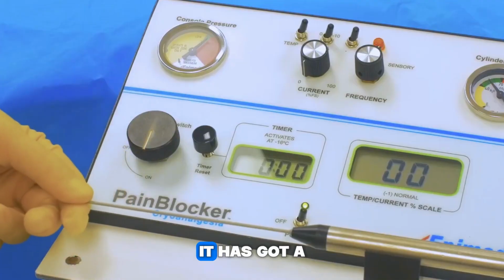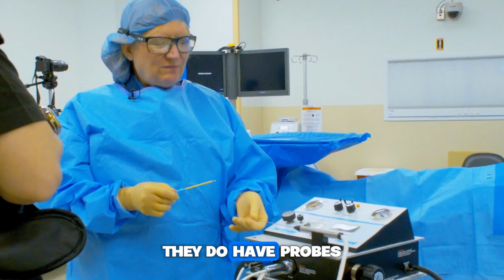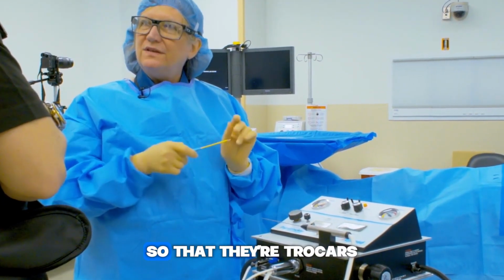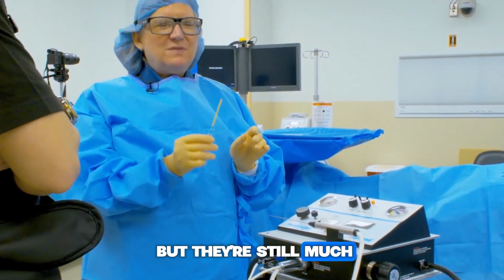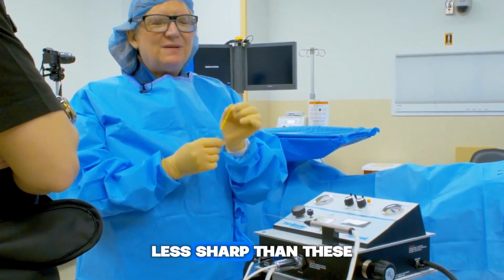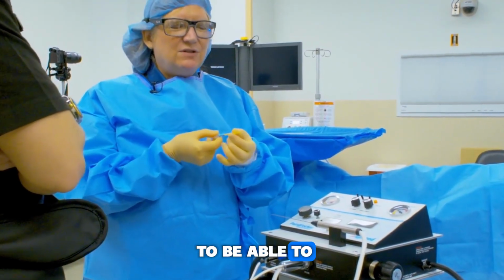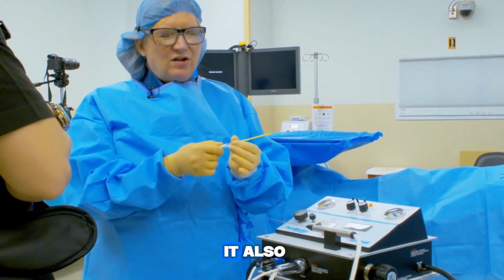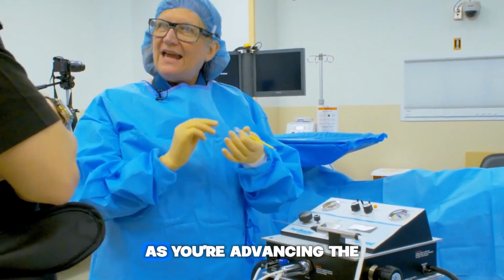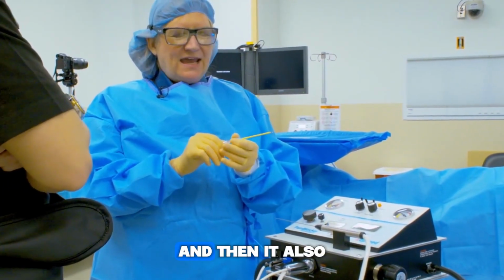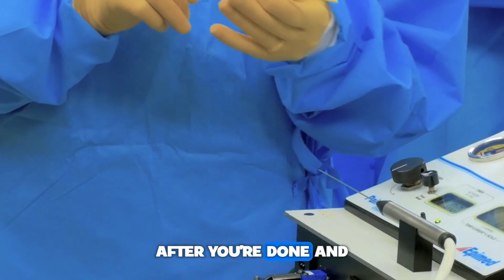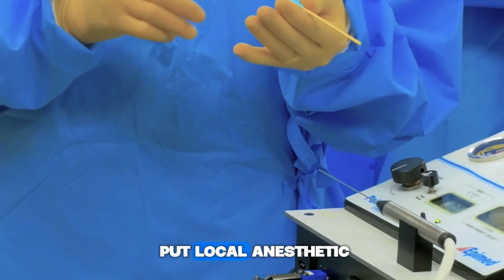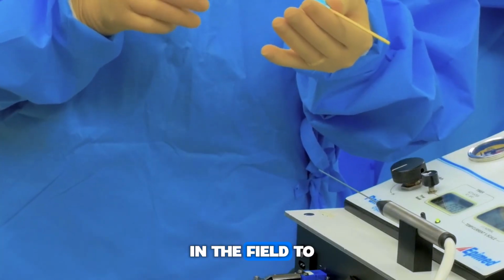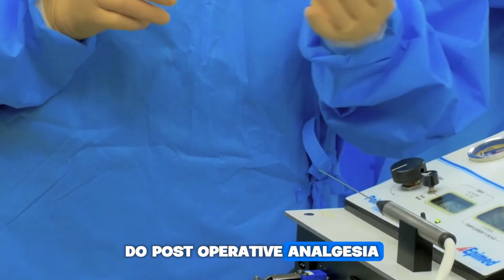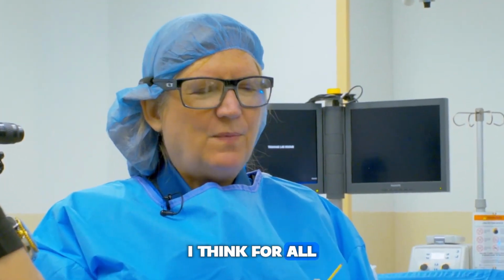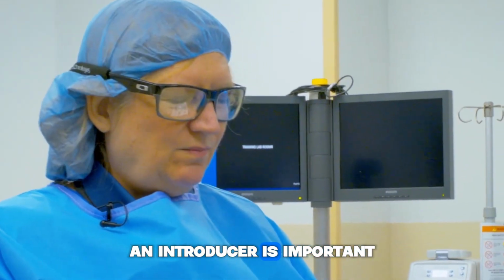You'll see that this probe has got a blunt tip. They do have probes that are diamond beveled so that they're trocars, but they're still much, much less sharp than these needles are. And this allows you to do a very atraumatic introduction. It also allows you to add local anesthetic as you're advancing the needle through the tissue. And the third thing is, after you're done and you've taken the probe out, it allows you to put a long-acting local anesthetic in the field to do postoperative analgesia from it. So I think for all of those reasons, an introducer is important.